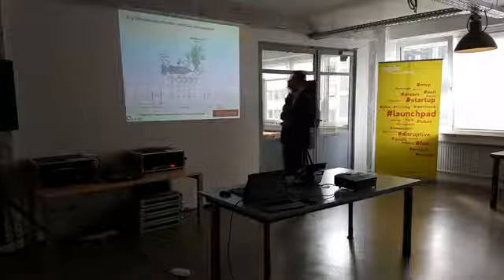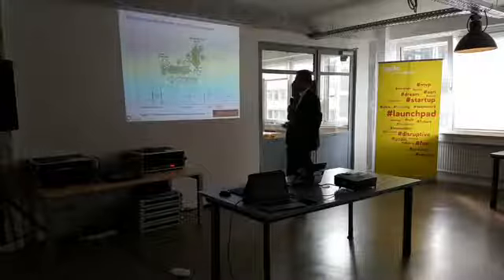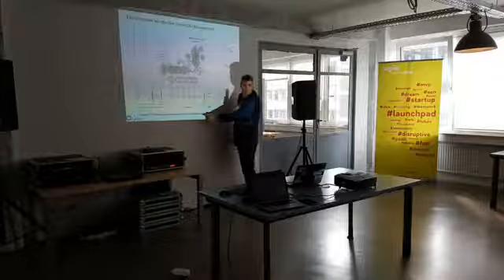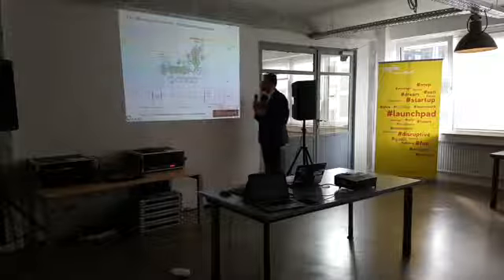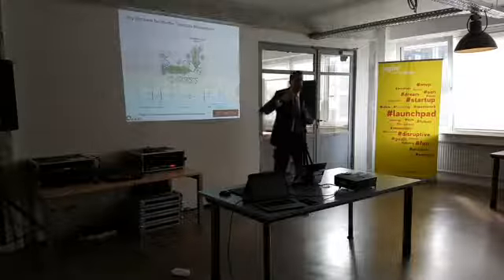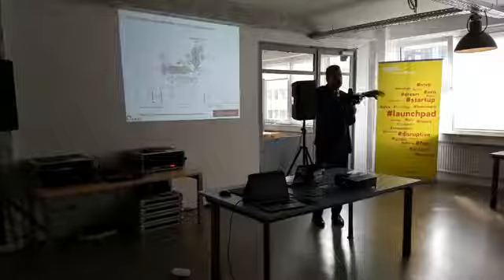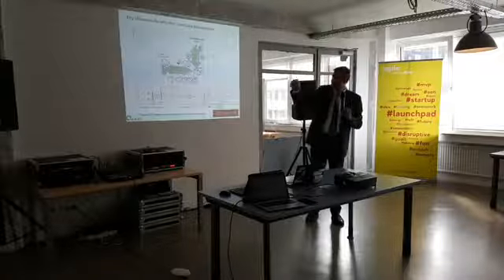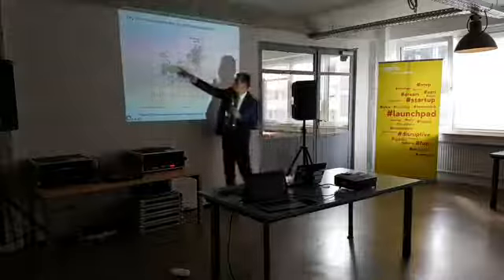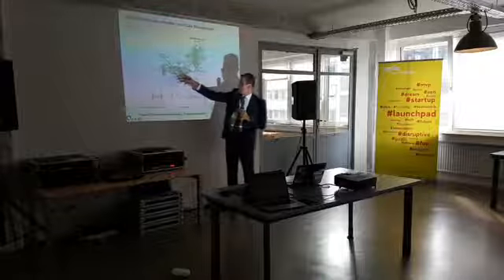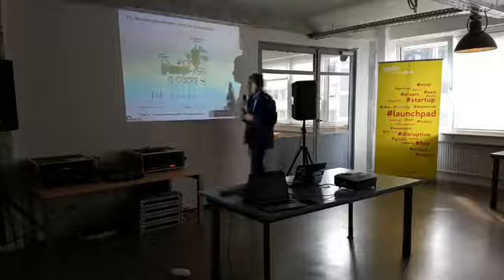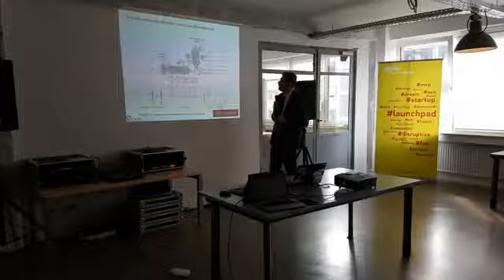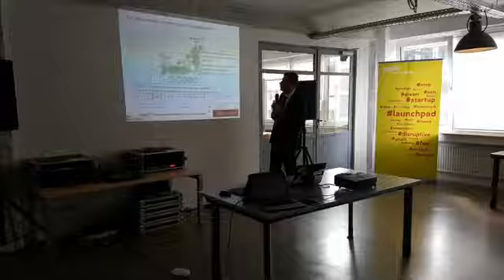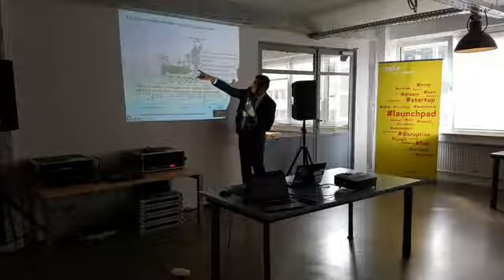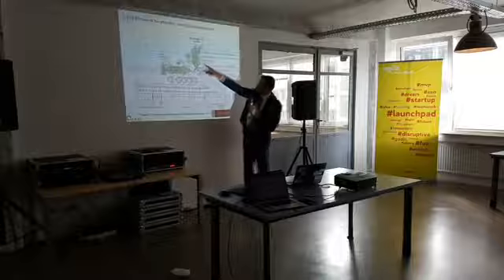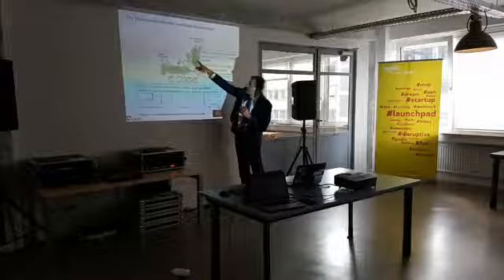The second one is the feeder automation system communication layer. In the communication layer - communicating between remote locations, the field, and the control room - you have to implement and base your system according to these standards. Almost all of them are based on the 61850 protocol. Communication between the field and operation is according to 60870 or 61850.